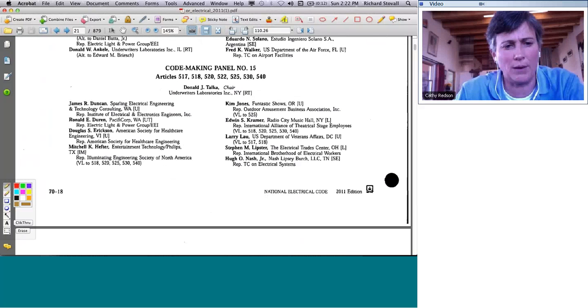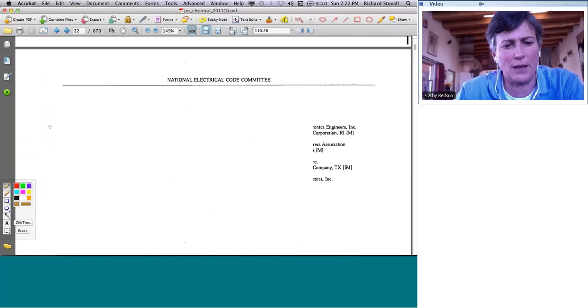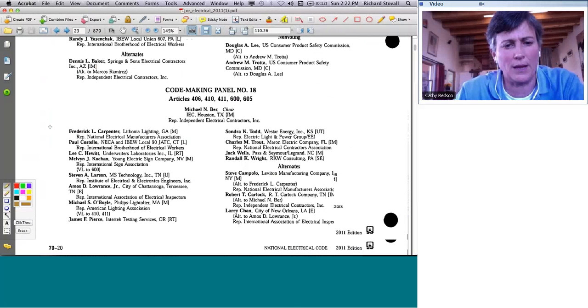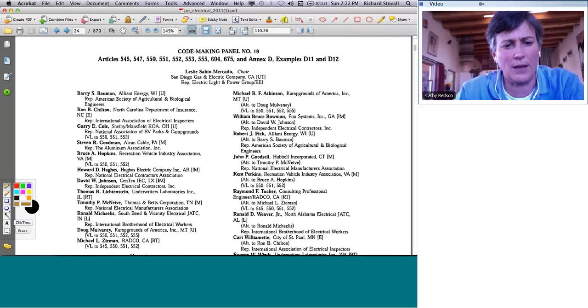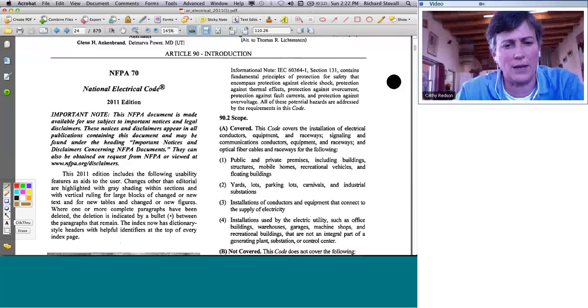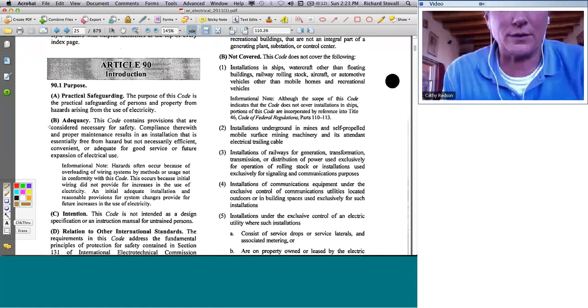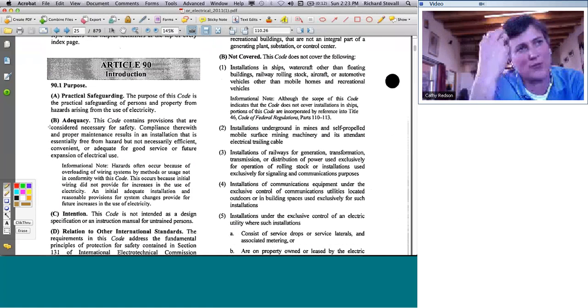I learned last year in my travels around the 7th District for the JATC that there are jurisdictions in New Mexico and in other parts of the country that are still operating under the 1984 edition of the NEC. I was on the phone with someone from SMA and arguing because in their Sunny Boy 700, there's not room for a separate grounding electrode conductor as well as the grounding conductor coming from the DC disconnect as well as the one going out to the inverter. There's only lugs inside the Sunny Boy 700 for two connections, and you have three.